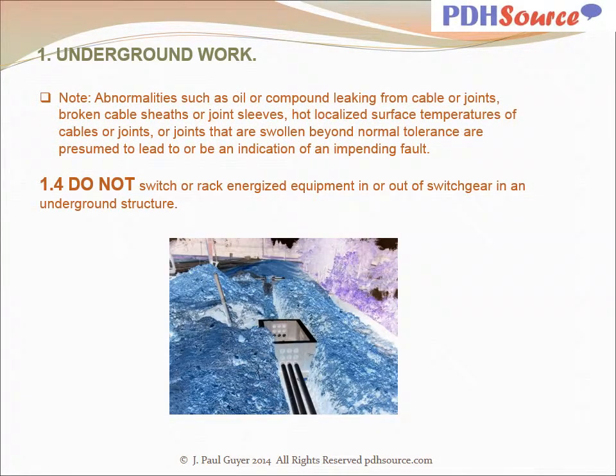Note: abnormalities such as oil or compound leaking from cable or joints, broken cable sheaths or joint sleeves, hot localized surface temperatures of cables or joints, or cables or joints that are swollen beyond normal tolerance are presumed to lead to or be an indication of an impending fault. Do not switch or rack energized equipment in or out of switchgear in an underground structure.